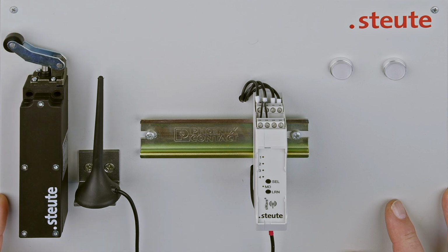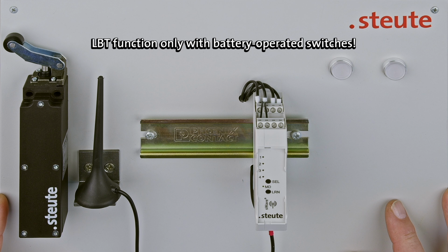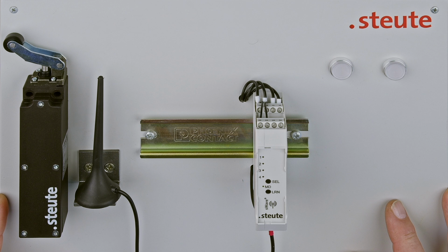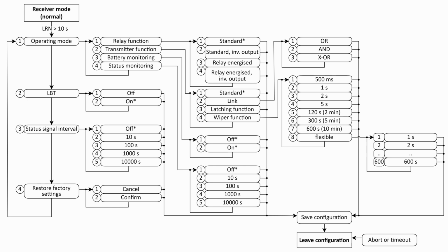Now we want to activate the listen before talk function. On newly delivered switches, the listen before talk function is activated by default. Here in this example, we have an RF96 wireless switch that does not yet transmit with this function. To program, we use the flowchart from the mounting and wiring instructions. We want to activate the LBT function on this switch. We look on the flowchart for the path we need to follow to do this. We find the LBT function as the second mode.